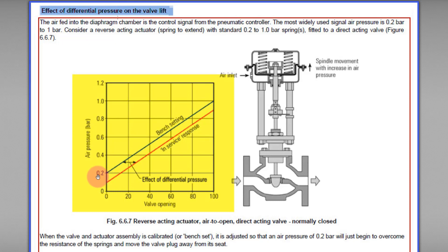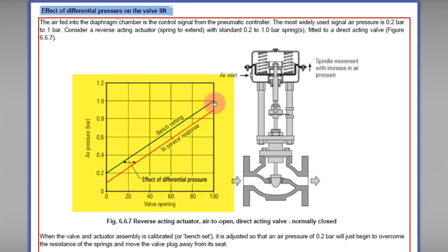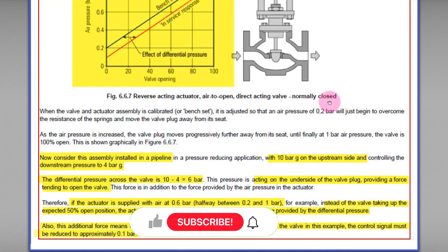The differential pressure provides additional force alongside the instrument air pressure, helping to push the valve plug outward — meaning it helps open the valve. So instead of needing more than 0.2 bar or 3 psi to start opening, you only need about 0.1 bar. And instead of 1 bar or 15 psi to fully open, you only need about 0.9 bar.